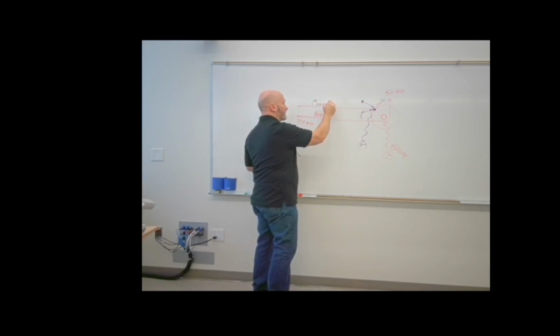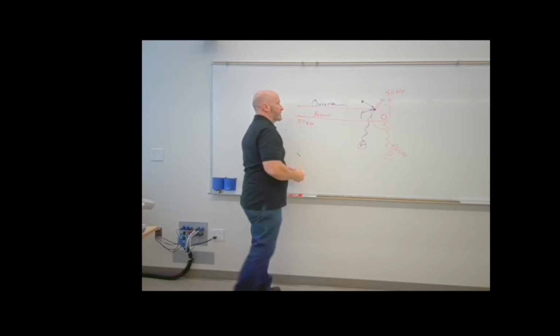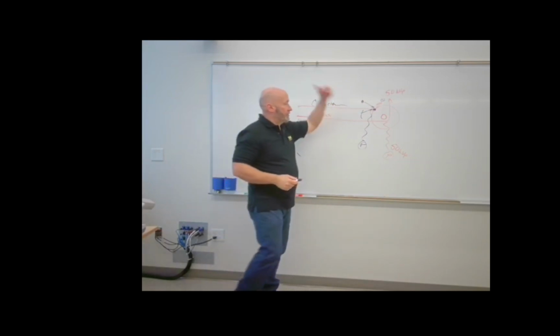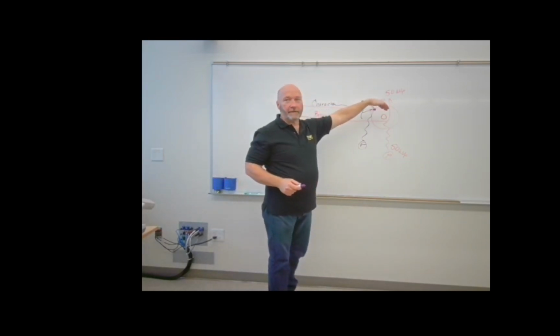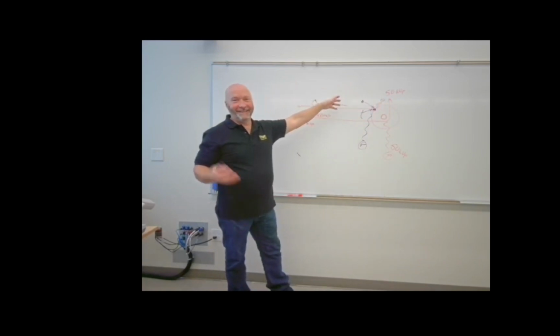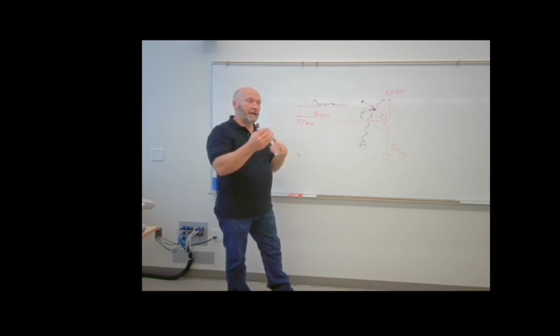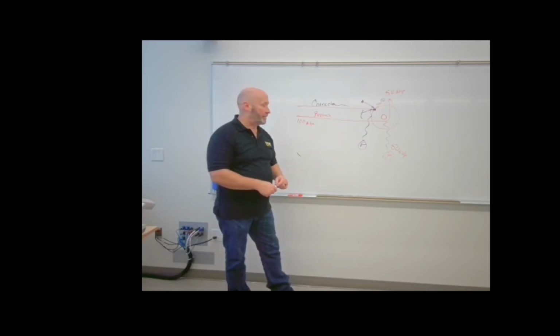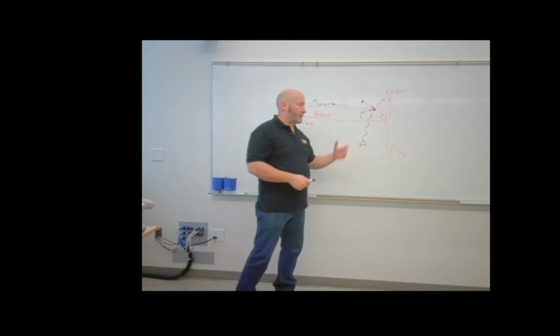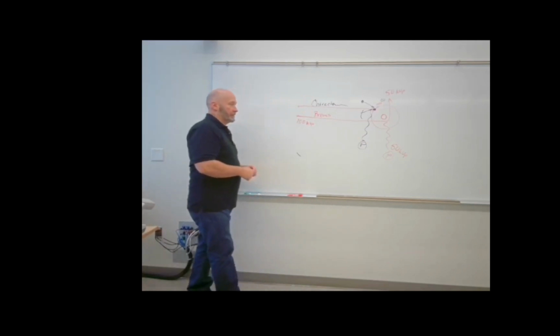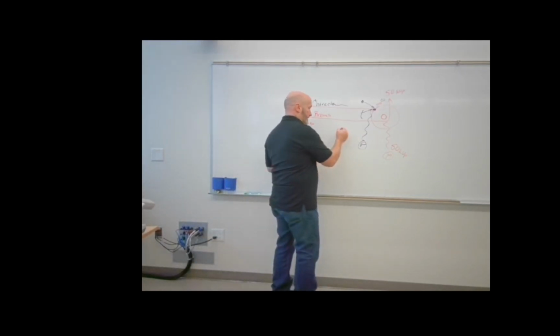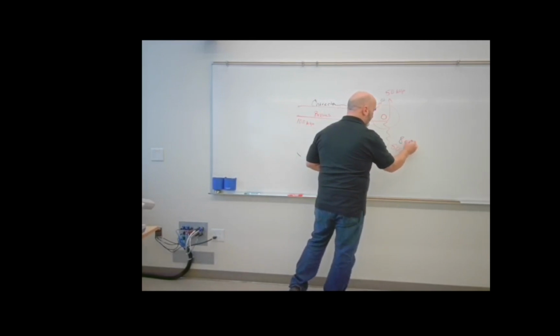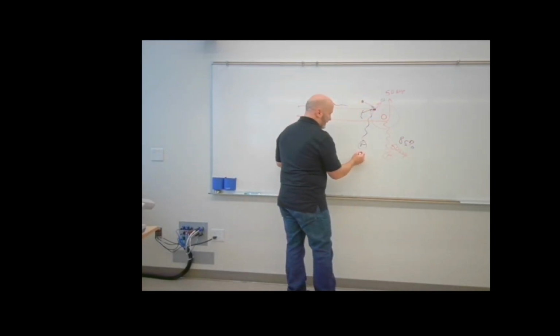And we call that interaction characteristic. Characteristic. So it's characteristic X-ray creation, and it's characteristic specifically of the, you get lost in spelling while you're talking, so, you know. And it's characteristic of the tungsten atom, right? So we changed the atom type, and we're going to change that up. So those are two different means of creation, and they say statistically, then that's 85% of our beam, and then this accounts for the remaining 15%.